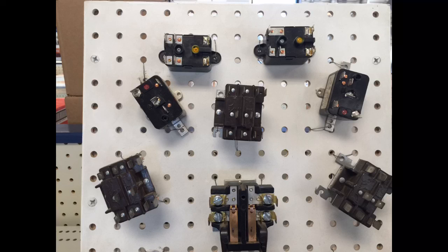Relays and humidifiers. The picture showing now is a variety of relays. They come with different numbers like 9290, 9293, 9380, and so on and so forth. But basically, a relay is not much different from a contactor. The only difference between a relay and a contactor, as far as my understanding goes, is that a relay has got normally open and normally closed contacts, and a contactor is pretty much normally open all the time.